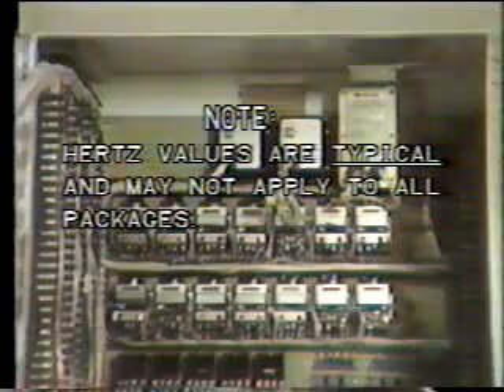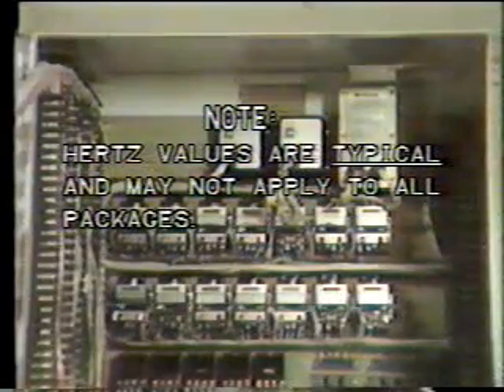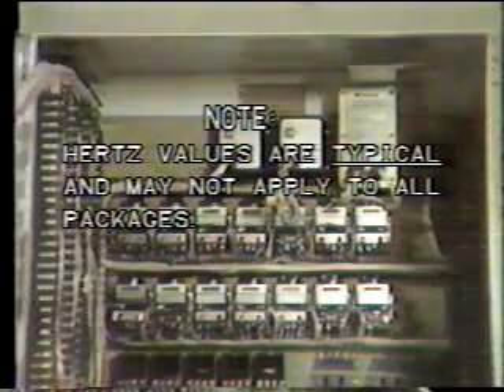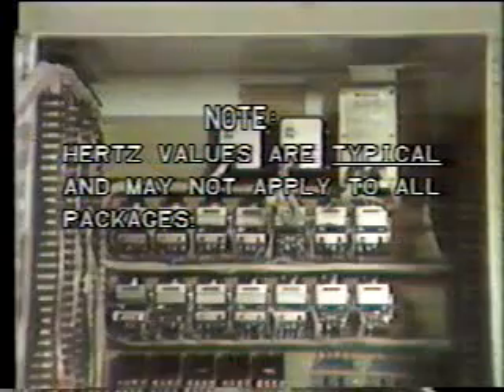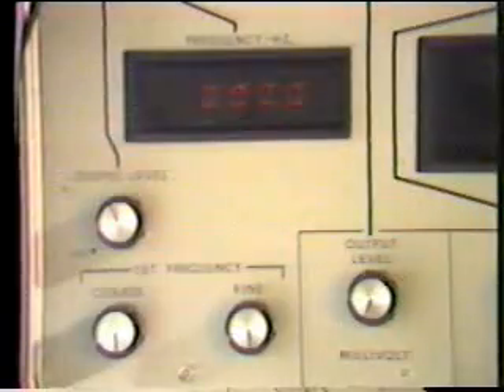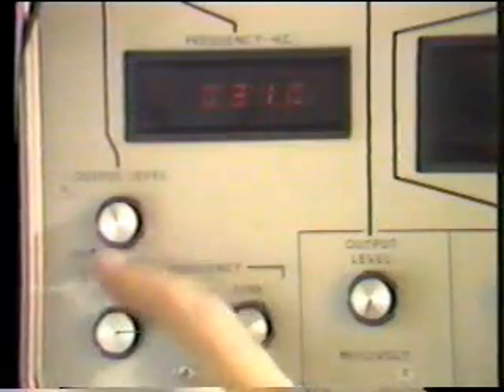In the following steps, you'll calibrate the engine speed meter at 100% speed. Note the Hertz values given for the set points in this job program are typical values which may not be the same for every package. Always refer to the electrical schematic to verify the set points for the package you're working on.